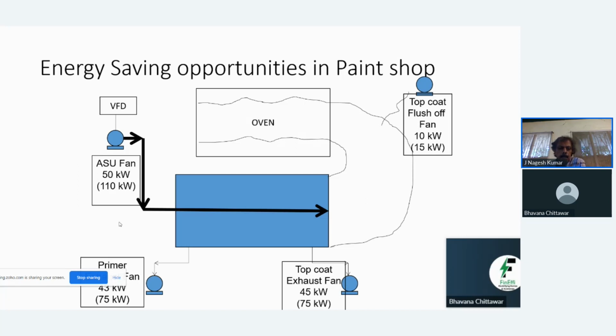Now the plant says we already have a VFD for the fan, so that option is over. We were looking for putting up a VFD for the fan, but the plant says they already have one in place, so nothing much can be done. The exhaust fans we measured were drawing 45 kilowatt on a 75 kilowatt fan. So now what to do?